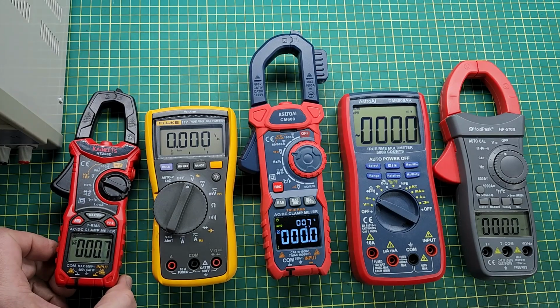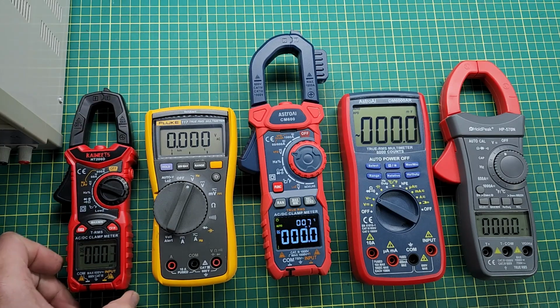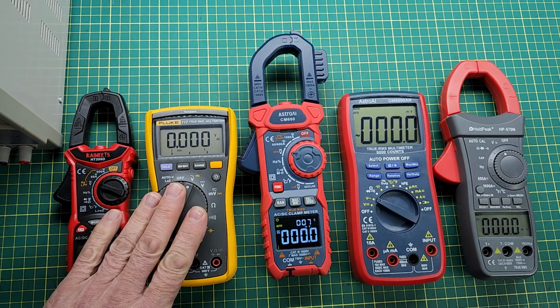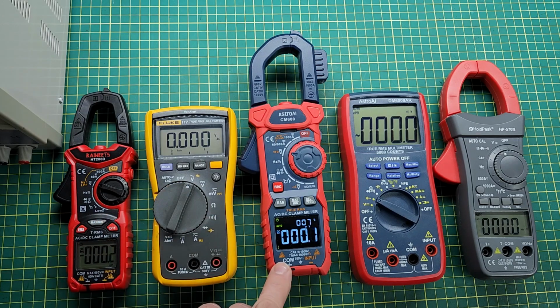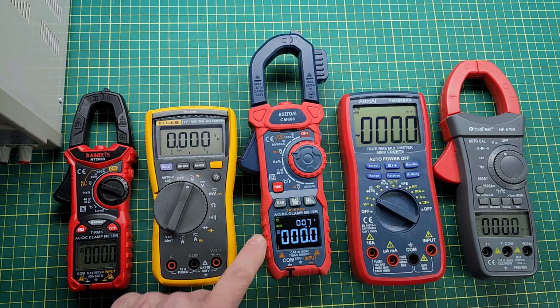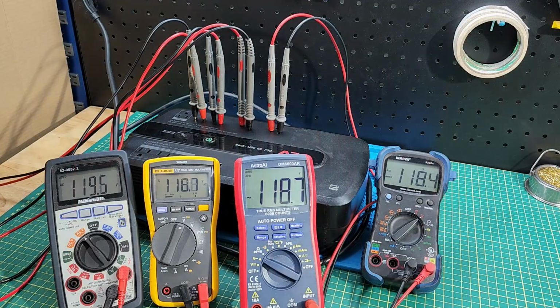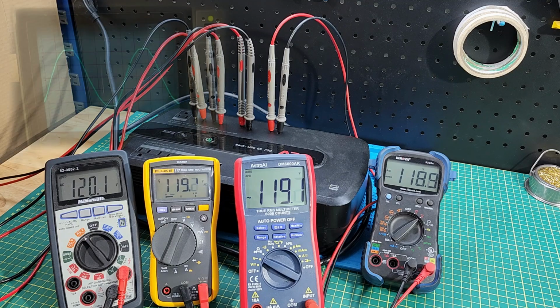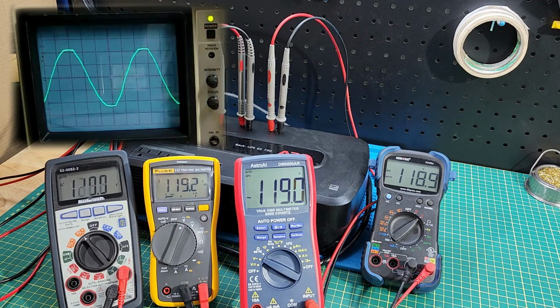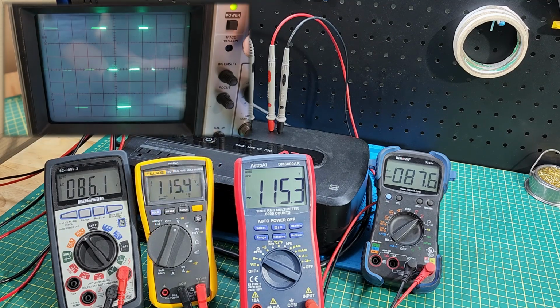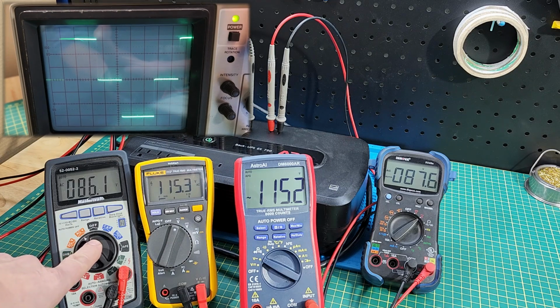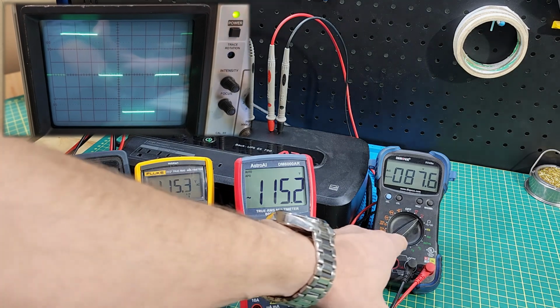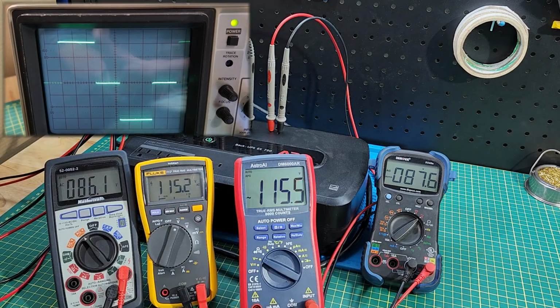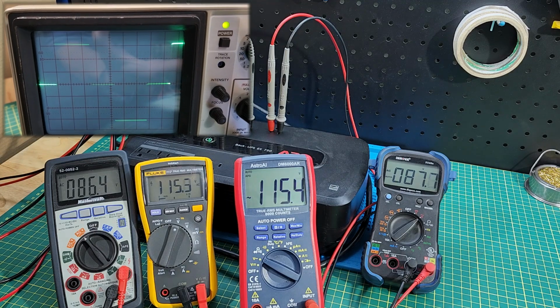True RMS meters are equipped with a more sophisticated algorithm that factors in the shape of the measured output and provides a true heat equivalent to the DC signal value. That is why non-true RMS meters are good only for measuring DC or sinusoidal AC signals. When the AC signal is not purely sinusoidal in shape, non-true RMS meters provide inaccurate readings.